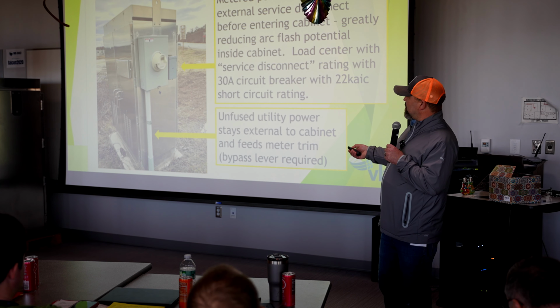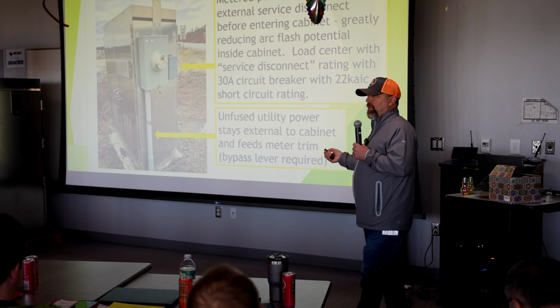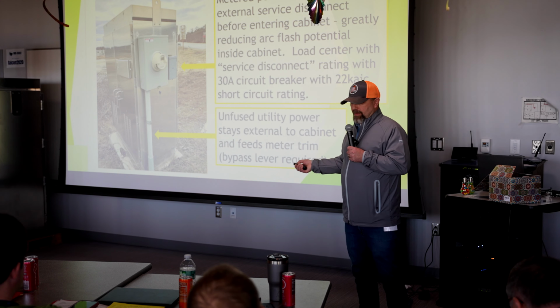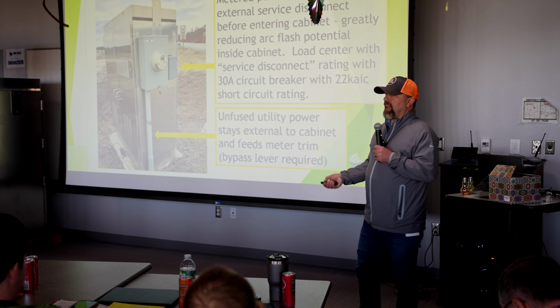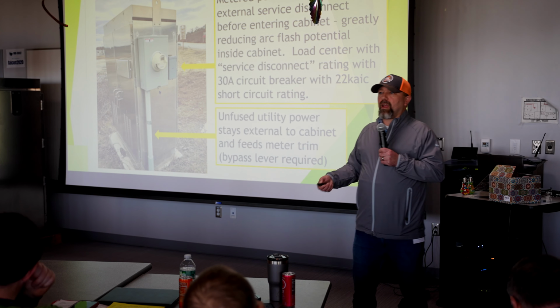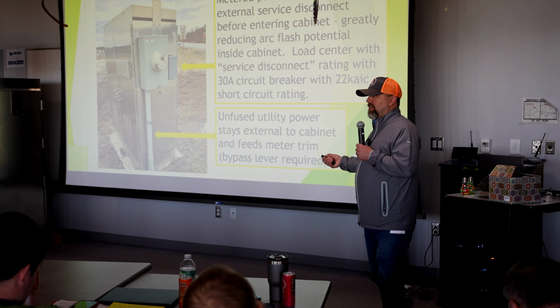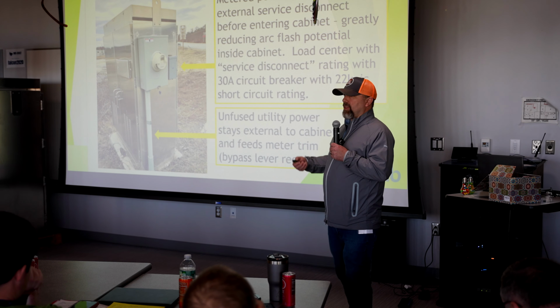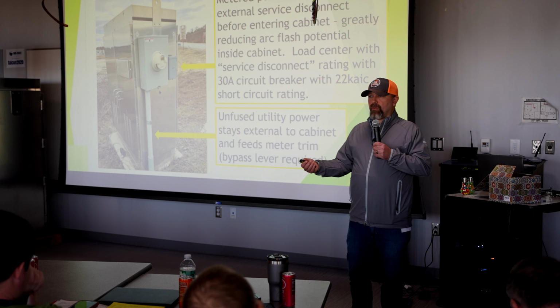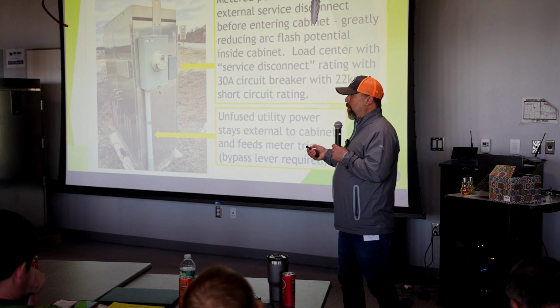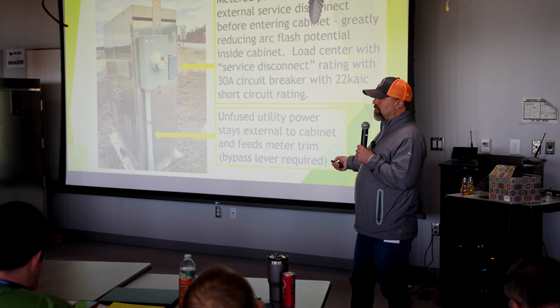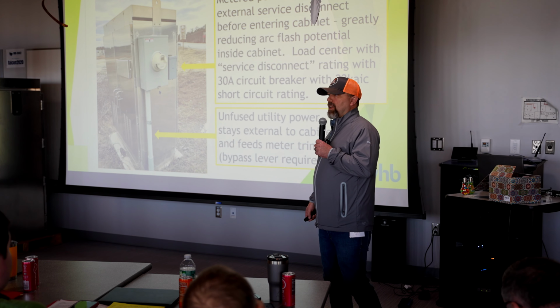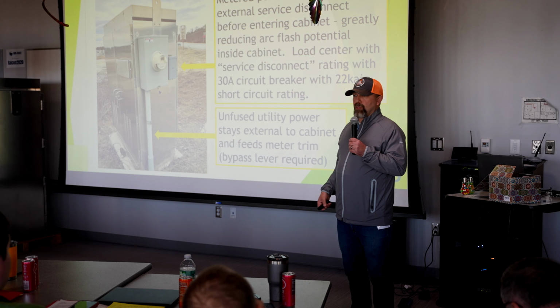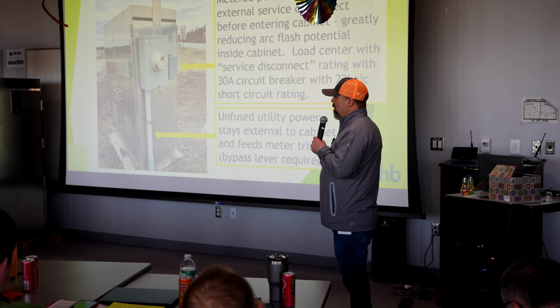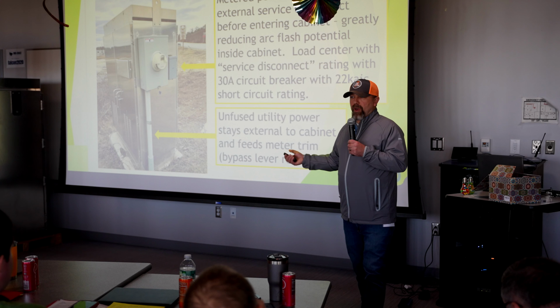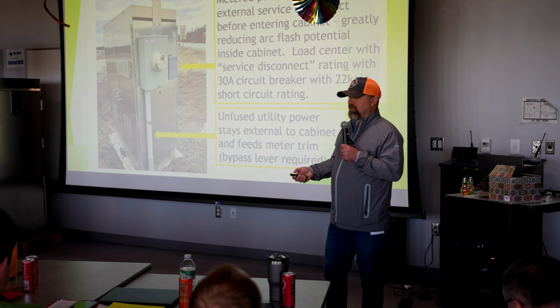And in most cases, when you're looking at the main breaker, 30 amps covers everything in this cabinet. If you're going to have lighting attached to this, there are some cases where there is intersection lighting that runs at 240. So you'll have to consider that this 2-position load center may not be enough, and you might have to expand to a 4 or a 6. But obviously, you just have to make sure it's rated to be a service disconnect enclosure.